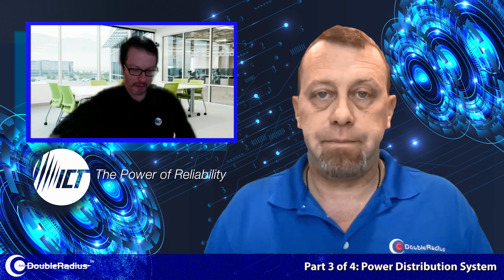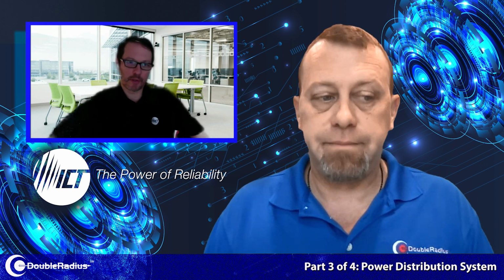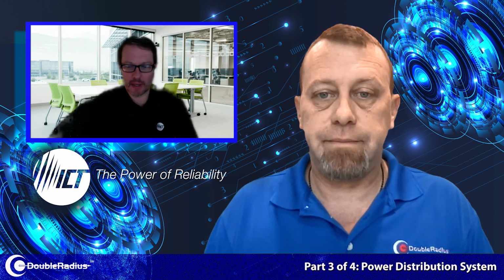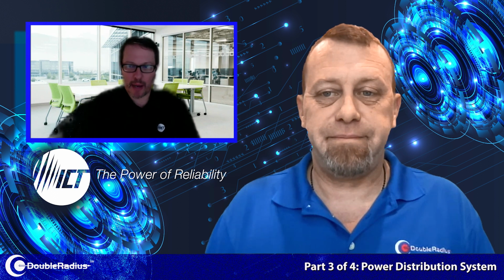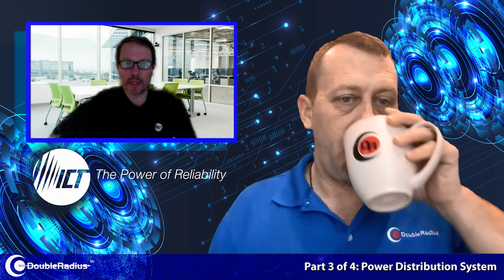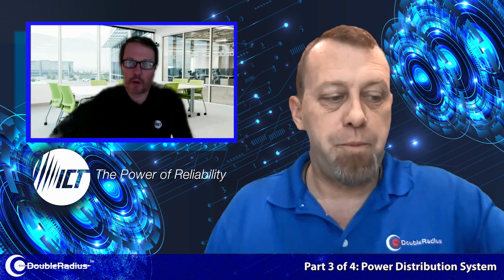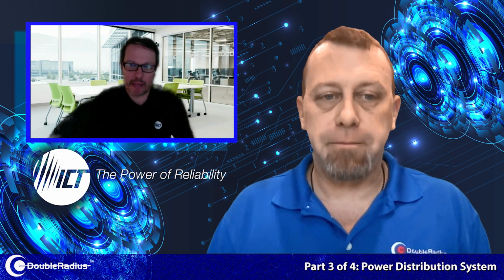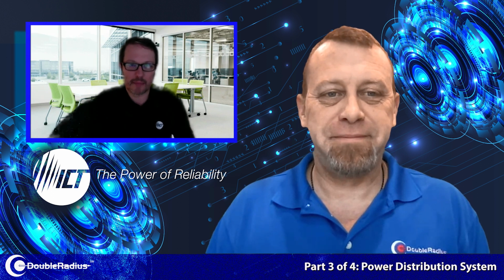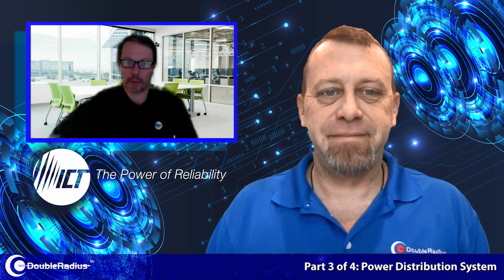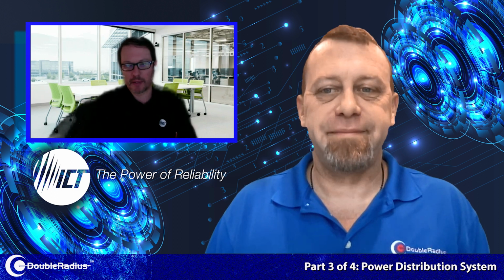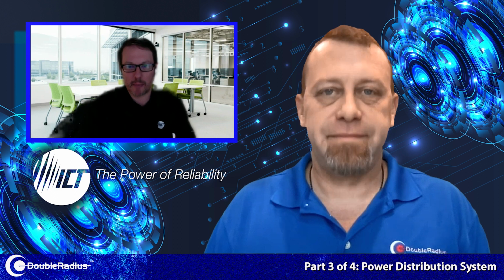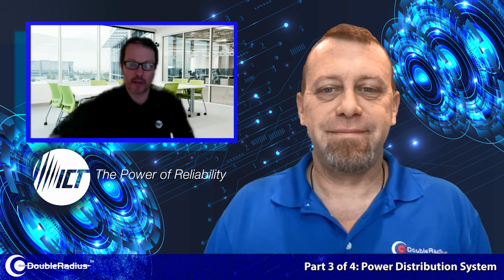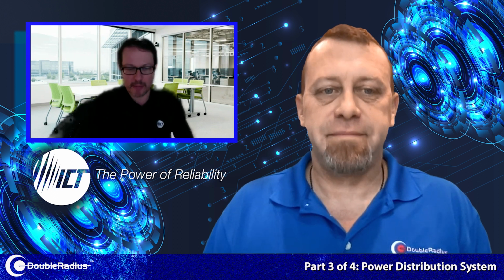Yeah, sure. I'll step back a little bit on the distribution side for folks that aren't familiar with that concept. We produce power supplies and power systems which provide a DC voltage used to power up load devices on your network, whether it's on the tower, at the base of the tower, wherever that may be. Quite often, if not always, there are multiple devices that require DC power. So typically with our solutions, we'll have one bulk DC power supply providing enough power to power up all of those devices. But in order to distribute that DC voltage to those multiple devices, the best and most effective method is to have a DC distribution panel.